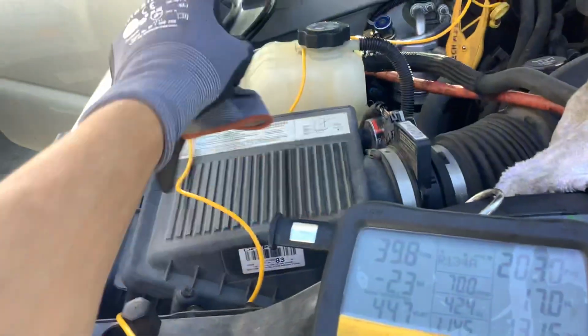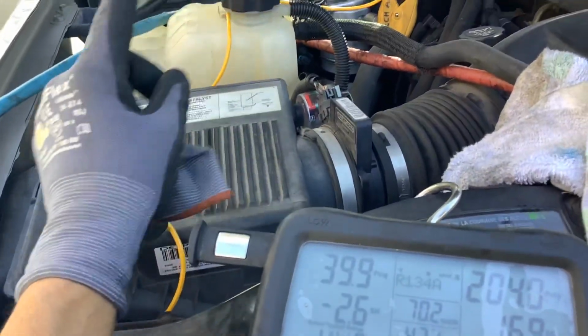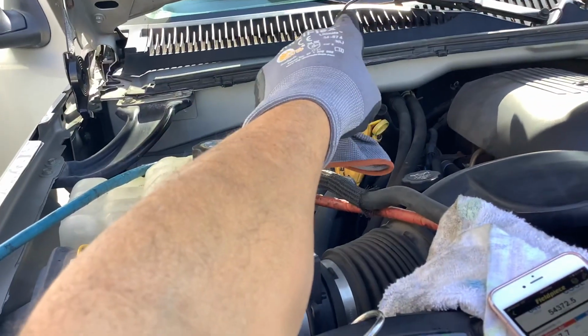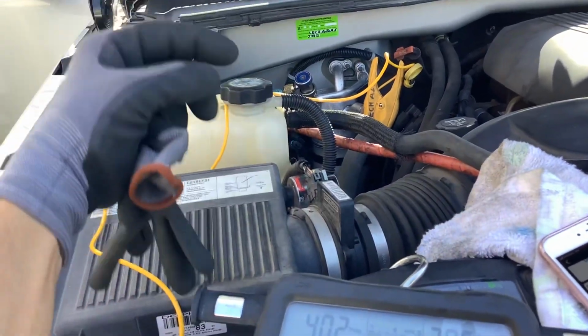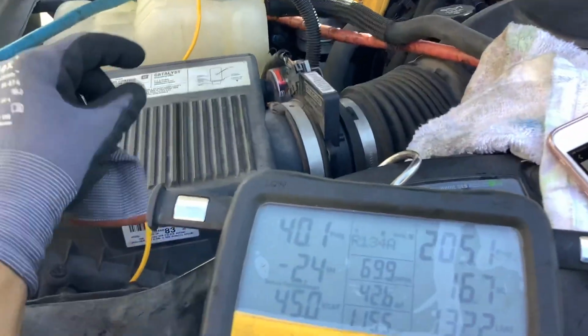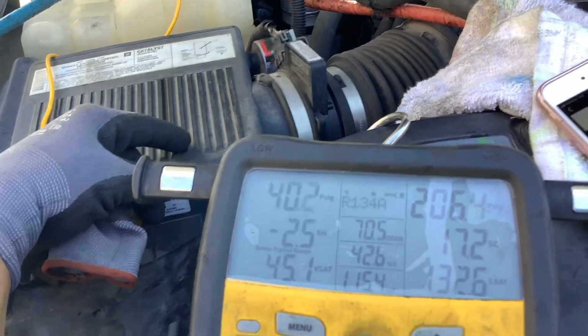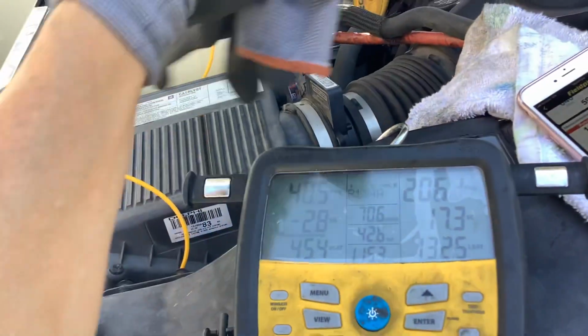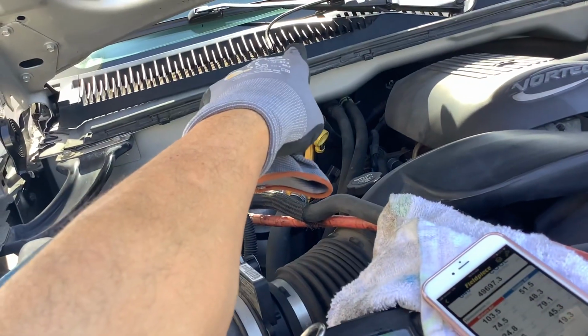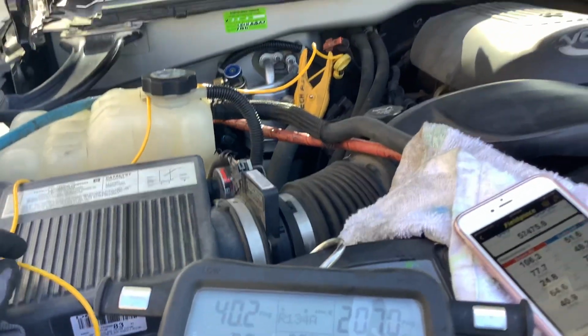Now the actual temperature, you see 100 degrees, 114 degrees here, but it's also pulling in cool air and mixing it from other locations, and you would get a mix. And if I take that temperature probe and put it down inside just at the inlet of the fan motor, you would probably see about 84, 85 degrees, even though the outside temperature is only 70. It varies on different year, make, models. That's why that is a very incorrect way of taking your ambient temperature for your heat load over your evaporator. As you can see here, coming down underneath, it's doing a really good job of condensating water.